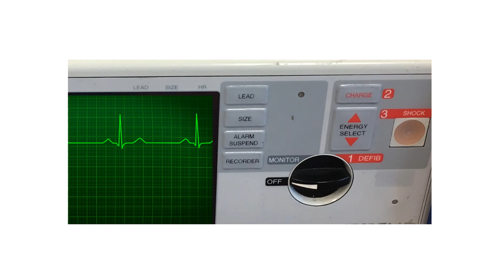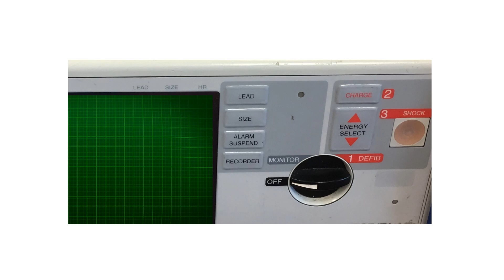The voltage may be as high as 2200 volts in a biphasic defibrillator and 5000 volts in a monophasic defibrillator. But the current is of the order of milliamperes and lasts only a few milliseconds. Most of the current day defibrillators are equipped with ECG monitoring facility as well, so that there is no need to connect a separate ECG monitor to identify the cardiac rhythm.